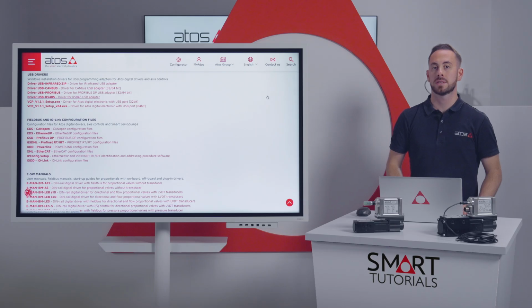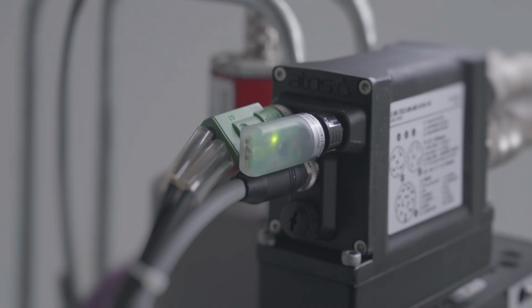If the blue LED on the EABTH adapter blinks twice, but the device still does not appear among available devices, it may indicate that the adapter is already connected to a client. In this case, further connections are not possible, and it won't appear during a search for new devices. Make sure that the adapter has not already been paired with another PC using standard Bluetooth pairing procedures. The adapter should never be associated with a PC, as this would prevent any other devices from connecting. Also verify that the adapter is not already connected to another client, such as a phone app.